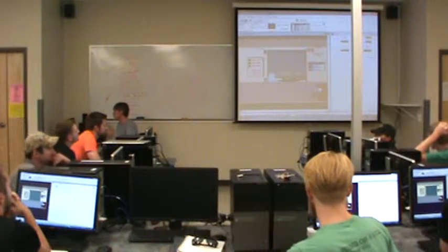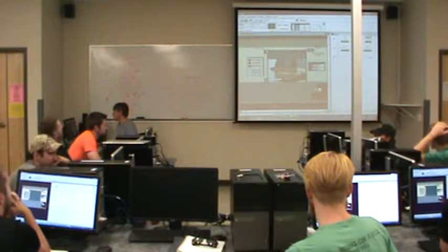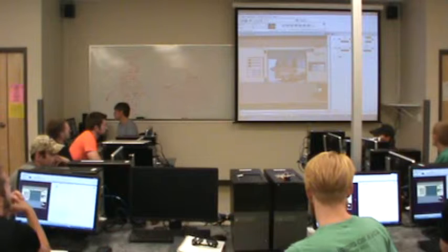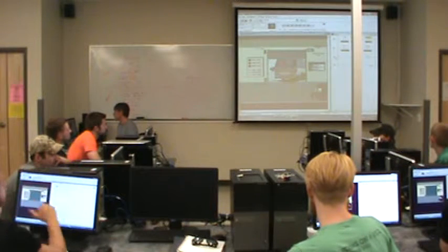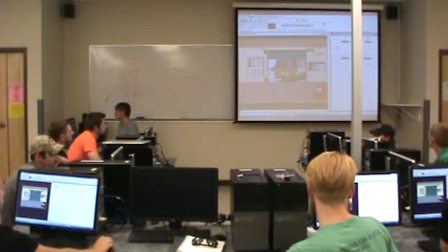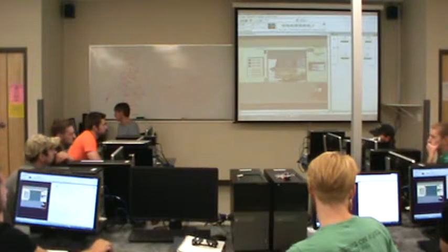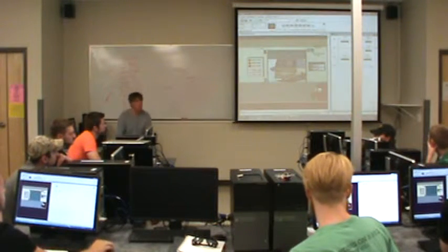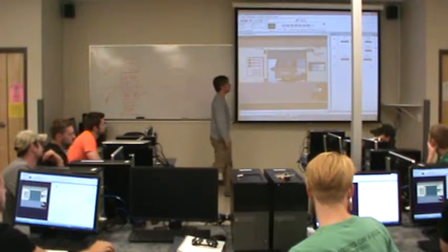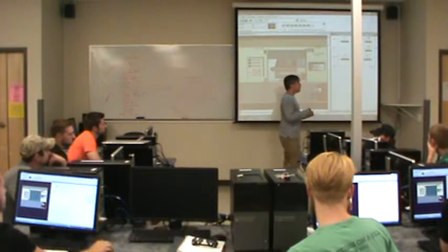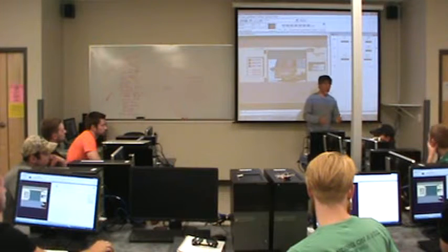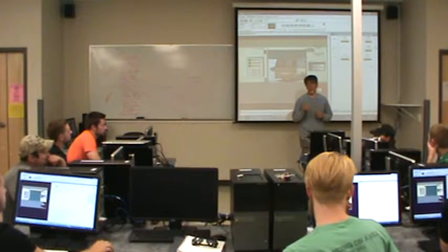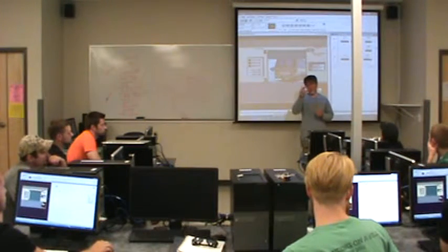So I've got to think a little bit more here. Okay? What I have to do is decide when it should be unlatched. Now I'm going to grab this rung and move it up and reorder rungs pretty easily. Okay? And I'm going to reference the same address. I don't like this. Most of the time, it is a mistake. Well, most of the time. For a beginning PLC programmer, it is a mistake to reference the same output two different places in the code.